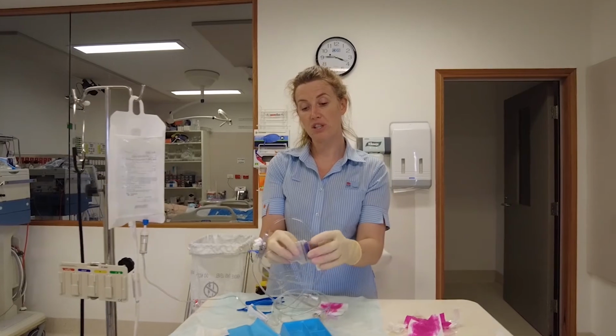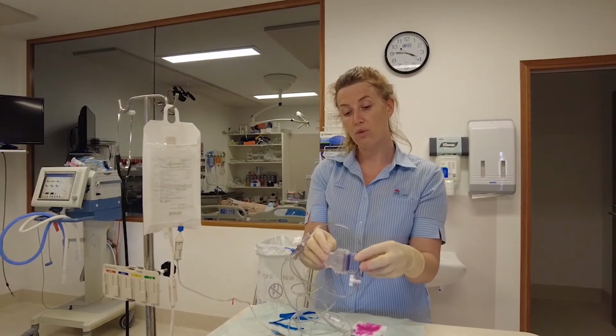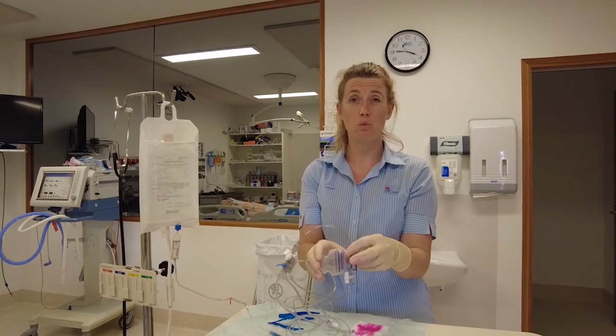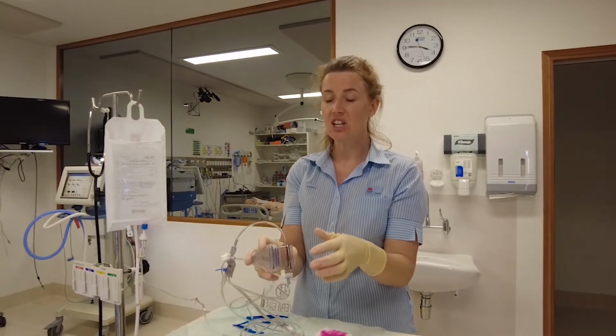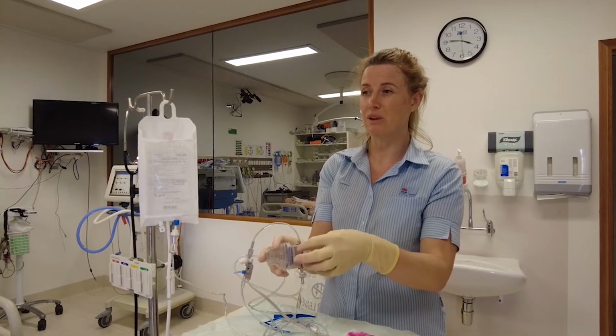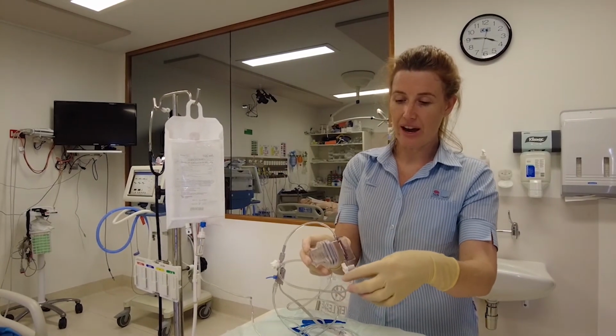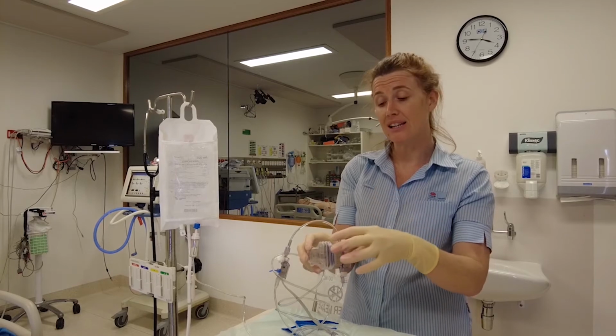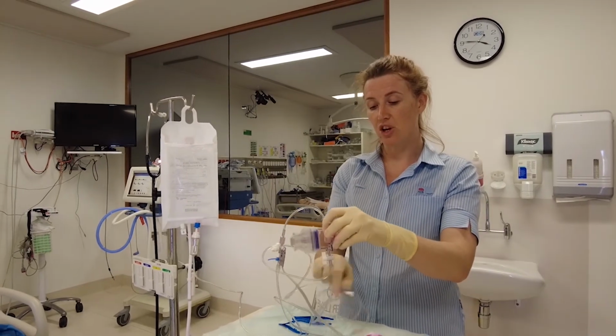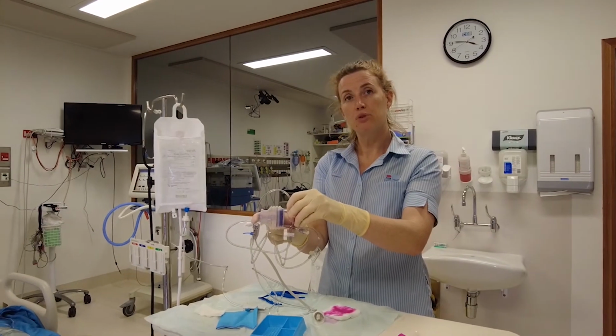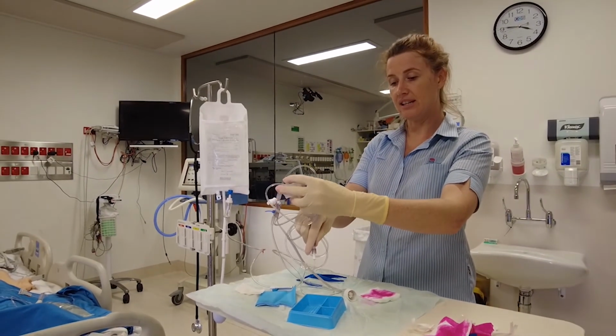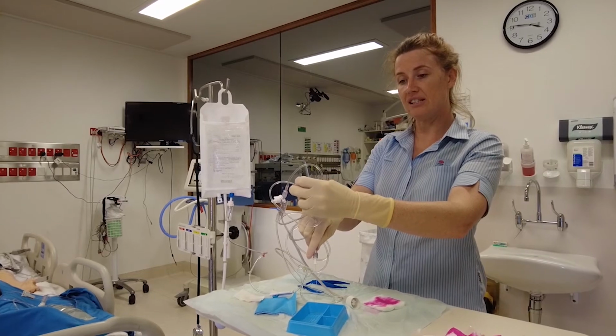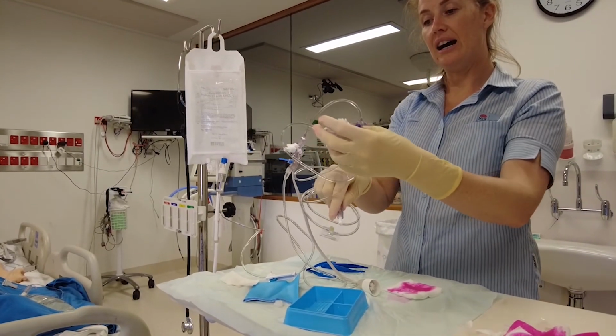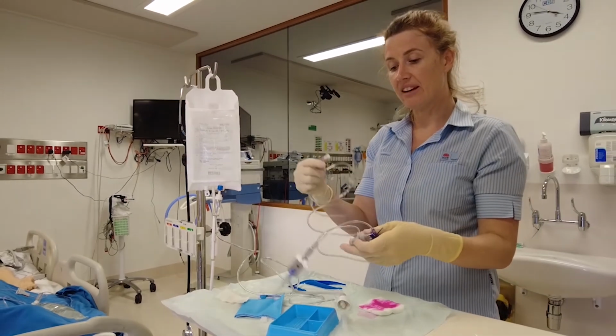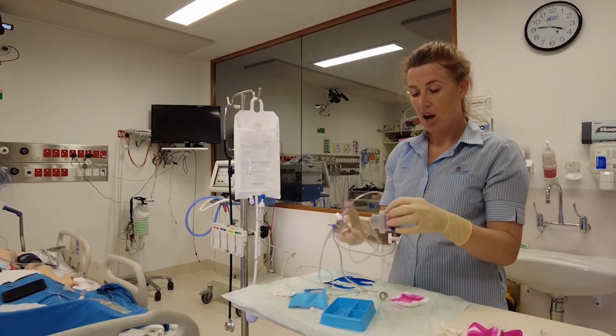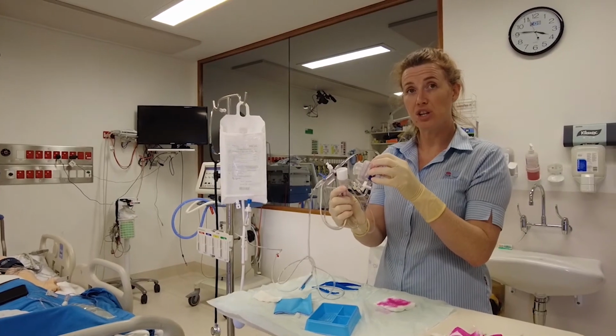Now two things, you can push this closed now that it's primed, or you can wait until it's connected to the patient, which is often what I do, because you know it's an arterial line. The doctors have aspirated blood through it. Sometimes when they take the syringe off to connect this line, they haven't clamped it, whatever, you might have some blood sitting in the arterial line. So I find once we actually go to connect this to the patient, I then push this in and give a really nice, big flush through that arterial cannula that's in the patient. And then I've got a nice clear arterial line. I can then hook up my actual pressure cable.